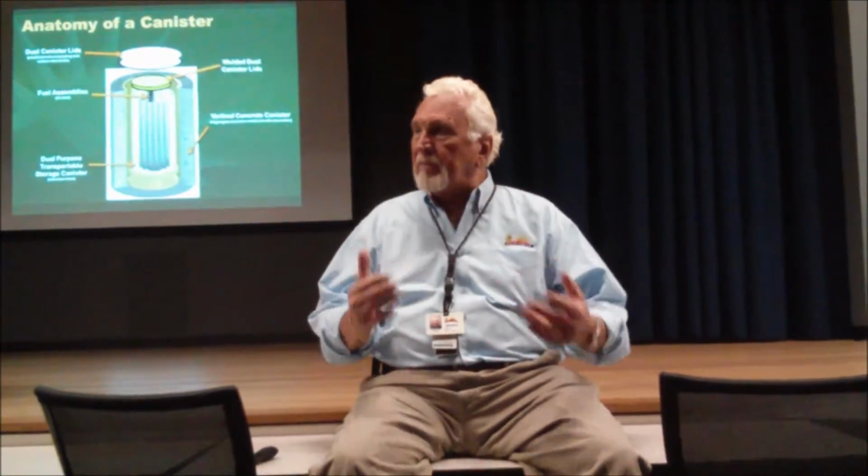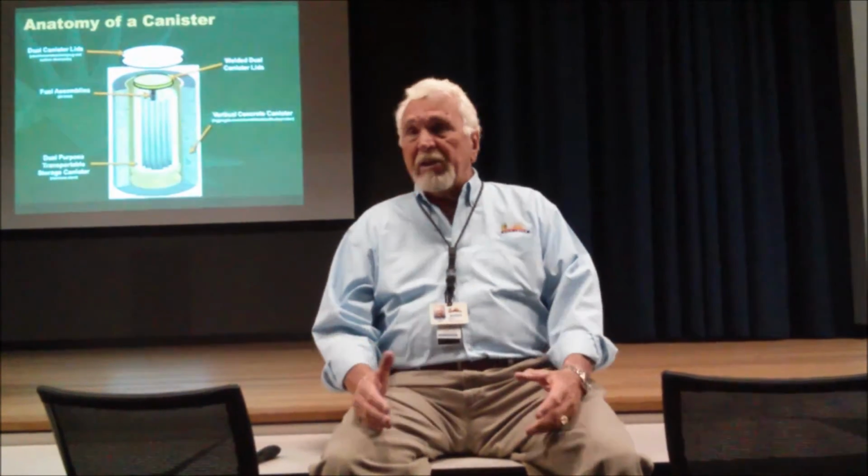Yes? So what happens at the end of the life of a plant that makes the plant no longer usable? The primary concern is kind of twofold. Number one, the technology has just gotten too old that you can't find replacement parts, and we're getting there on that. You can't find components to replace those that have worn out. Keep in mind, we have to have the same stuff because that was the approved design. So you can't find vendors. The other thing is something called neutron embrittlement. The steel pot that all the fuel is in, we call it the pressure vessel, is really just a carbon steel pot that's fully lined with stainless steel to prevent corrosion.